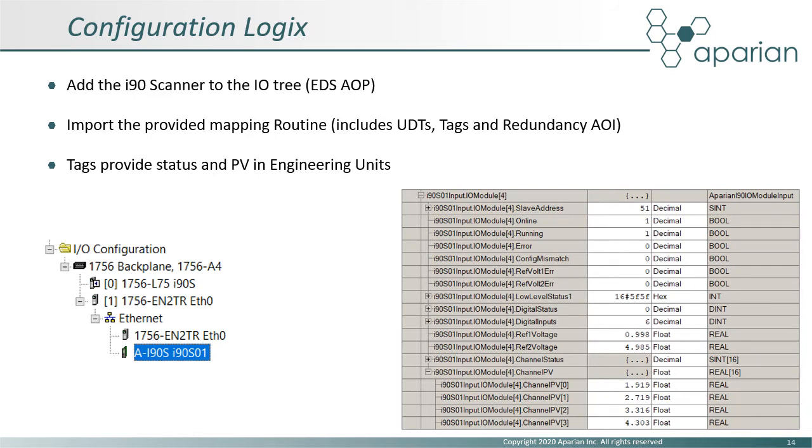The i90 scanner can be added to the Logix IO tree by using the EDS add-on profile. The EDS file can either be downloaded from the Aparian website or uploaded from the module itself. A mapping L5X routine is also provided, which includes all the required user-defined data types, tags, and the redundant scanner add-on instruction. All the scanner and IO module data and status information is available in the resulting tag structure.